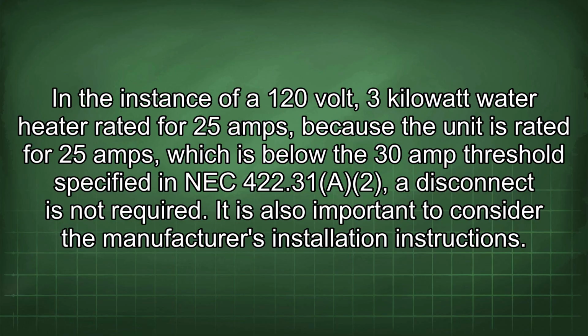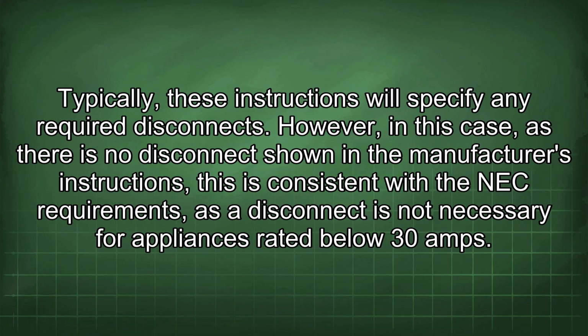It is also important to consider the manufacturer's installation instructions. Typically, these instructions will specify any required disconnects. However, in this case, as there is no disconnect shown in the manufacturer's instructions, this is consistent with the NEC requirements, as a disconnect is not necessary for appliances rated below 30 amps.